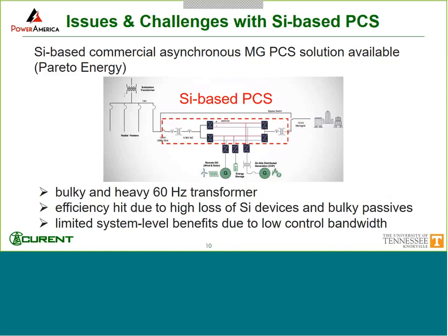In fact, some companies have already developed solutions using silicon technology for asynchronous microgrid. This is an example of Pareto Energy, and in their case, they use an IGBT-based approach. You can see the system here, they have a 3.3 kV AC system because of the limitation of the IGBTs. They use a transformer from 13.8 kV to 3.3 kV. And then that is the commercial solution.